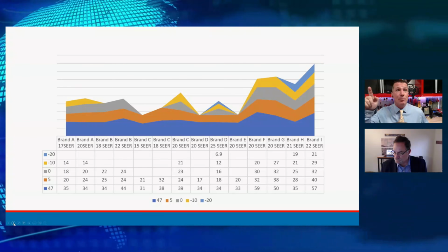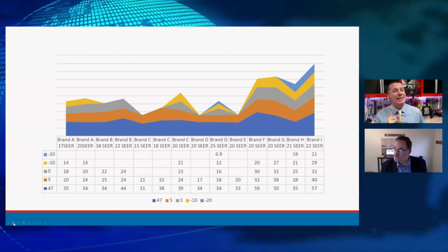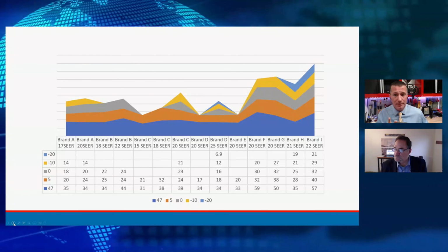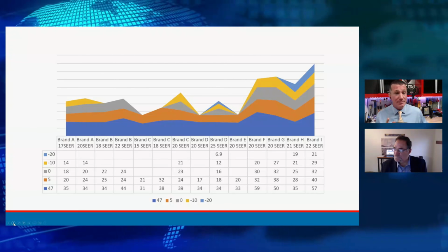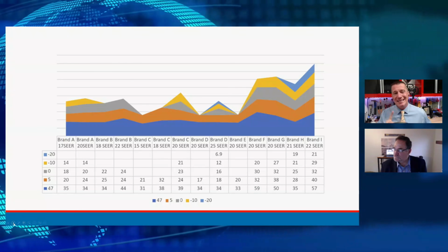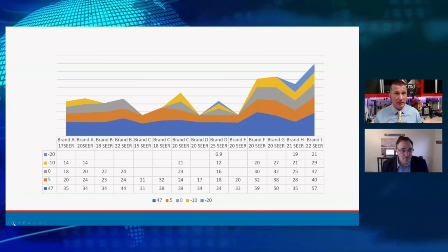And if we go to the same brand right next to it, yeah, their 22 SEER produces more heat. The downfall of that particular piece of equipment, the 22 SEER, we can all imagine what the price is on that, right? It only goes down to 0 itself. So it's not designed with the cold climate, high capacity operating condition.